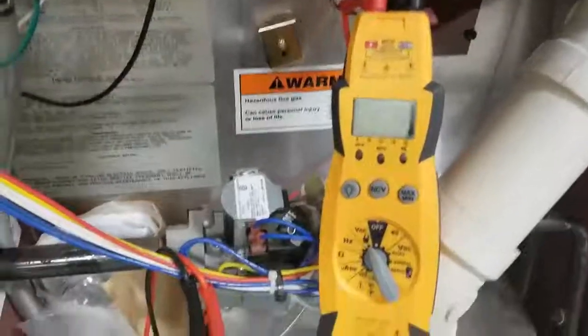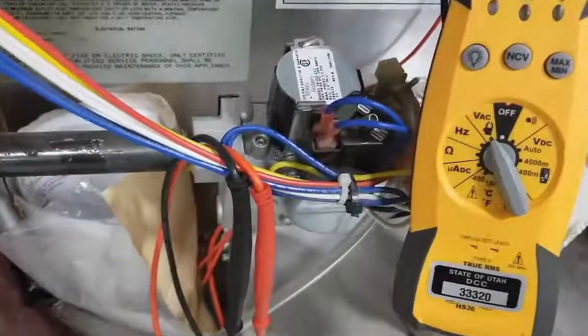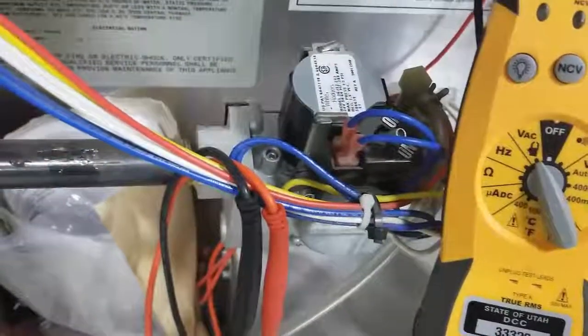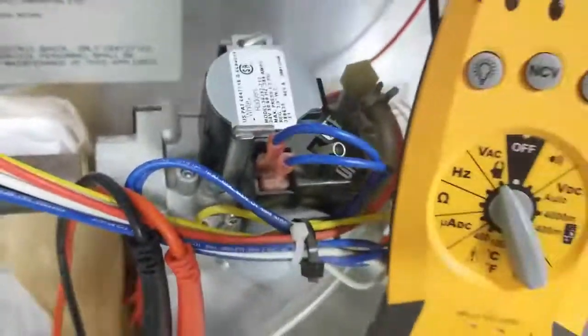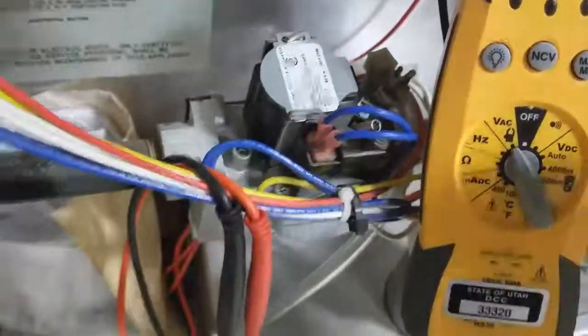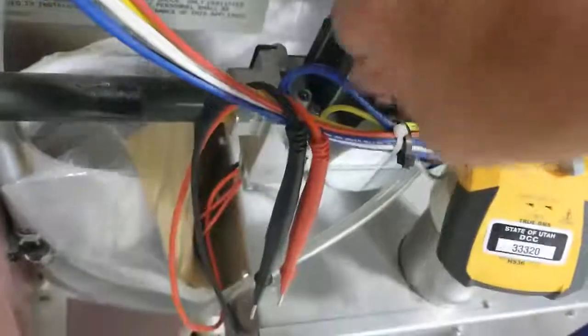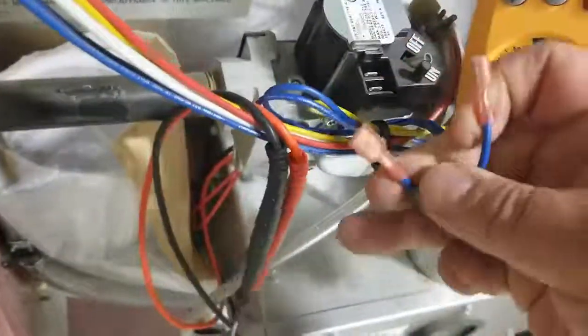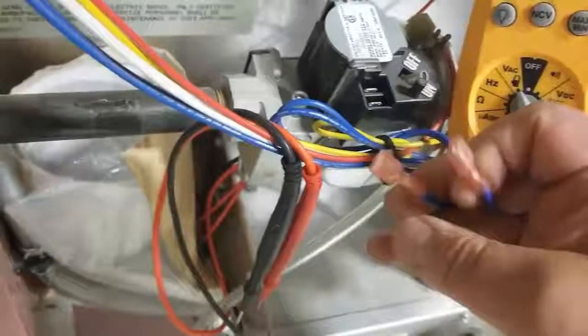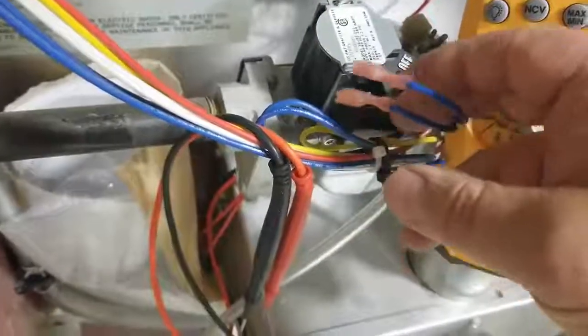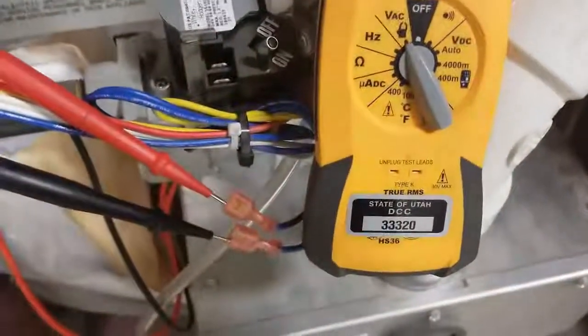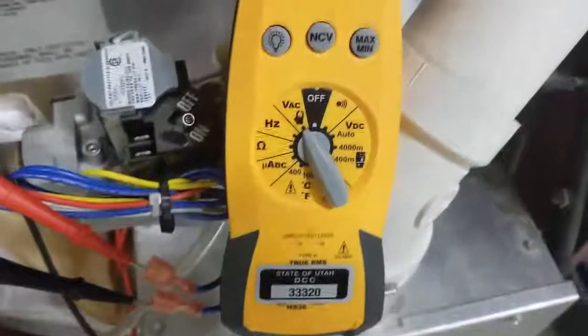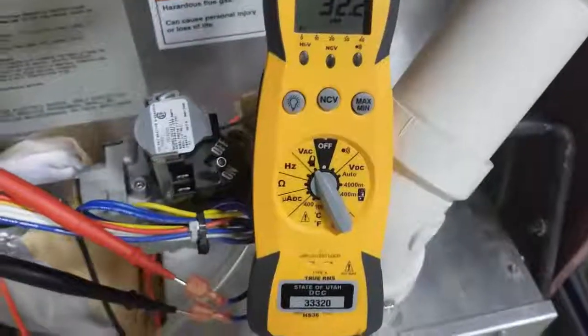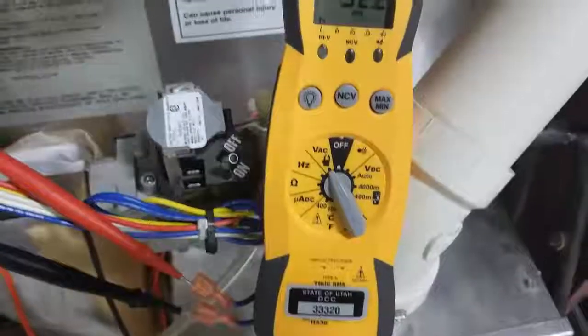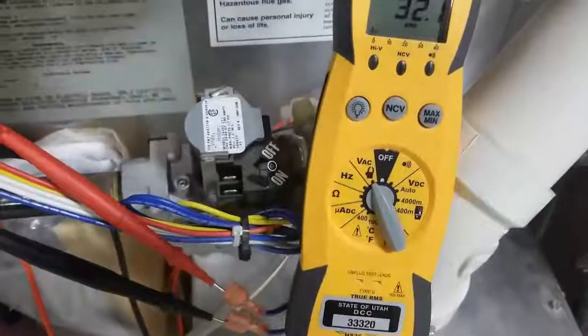Okay, next thing I want to check is to see if we have 24 volts going to the gas valve. You see our gas valve has 2 wires to it. So all I have to do is unplug those wires and then go ahead and hook my meter directly to those wires. Okay, I've hooked my meter probes to those two wires. I'm set for volts AC. We're going to go ahead and flip the unit on and call for heat.